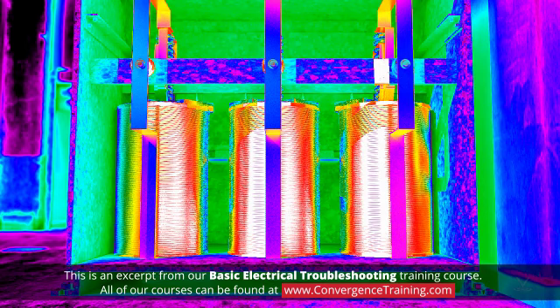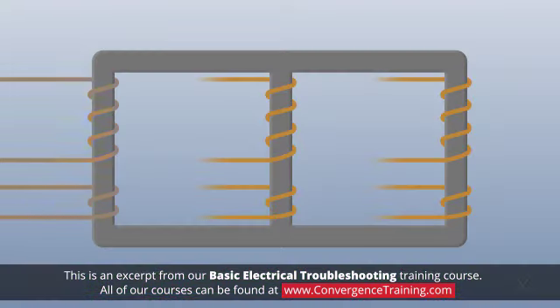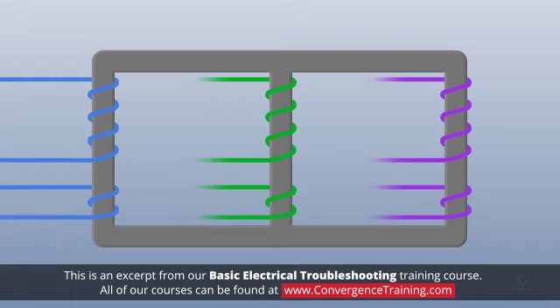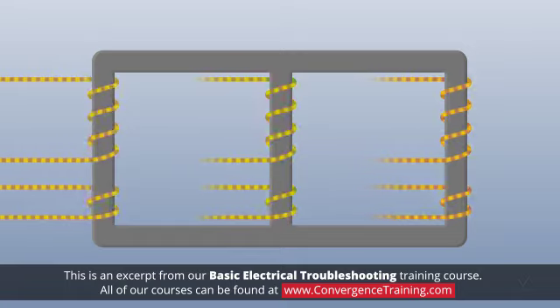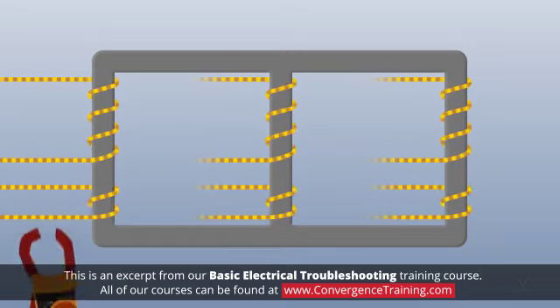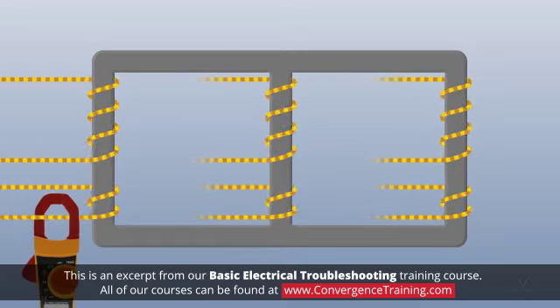If one leg of a transformer is not conducting current, the transformer will overheat, as does a motor with the same condition. Just as with a motor, all of the phases of a transformer should have a very similar voltage with respect to ground and should show a similar current flow when measured with a clamp ammeter.